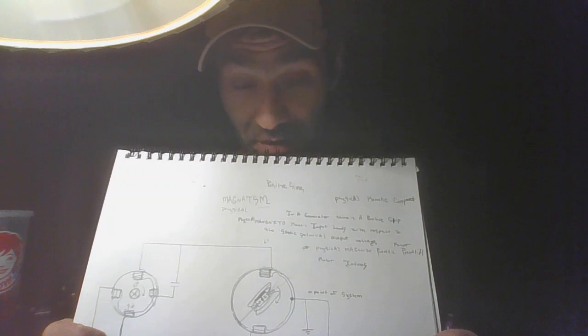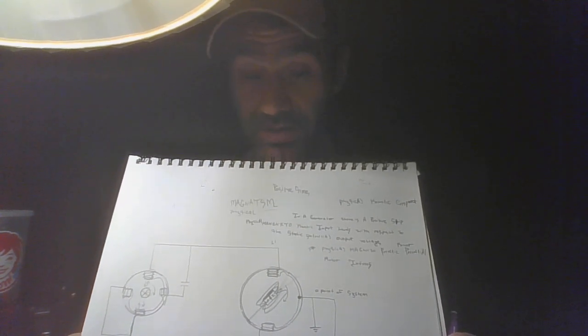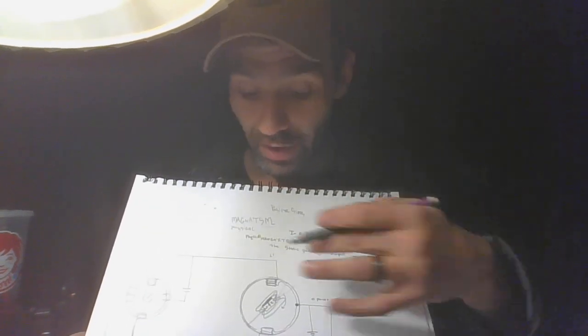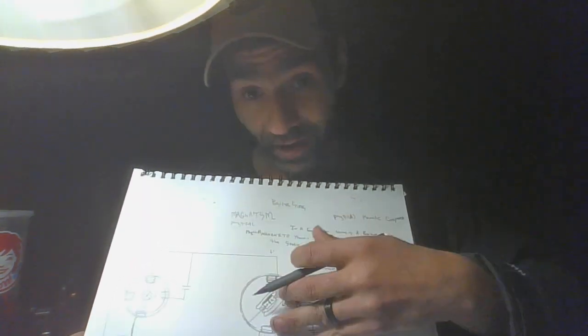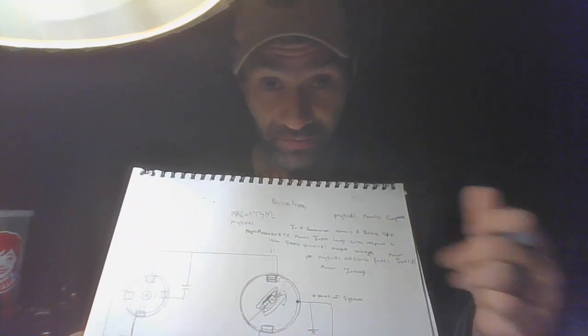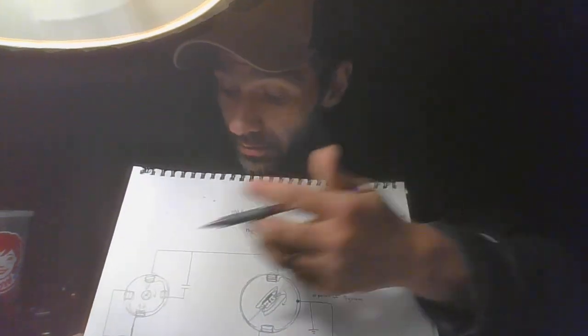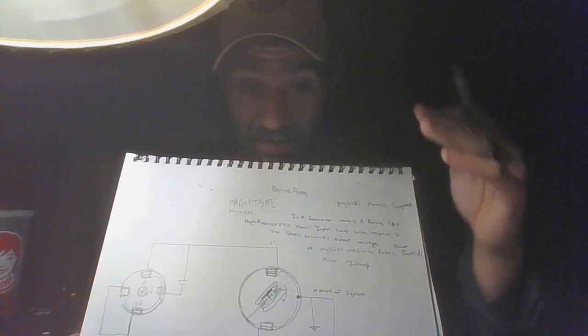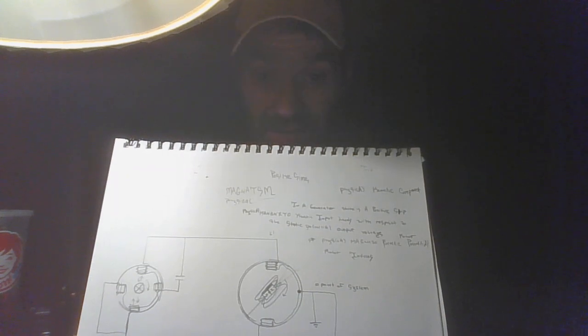We can't get 360 degrees of rotational torque out of it. We cannot create 360 degrees of rotational torque with a single phase supply, because we only have 180 degree in-phase displacement. We don't have a phase to phase voltage. We have to have phase to phase voltage between these windings to create the phase angle kick that's required for 360 degrees of rotation. Now, there must be this lag in an electric motor. The rotor, the donkey, must stay a certain distance behind the carrot. And if the donkey ever catches up to the carrot, there's zero torque on the rotor. And if the rotor outruns the stator's RPM, then the stator will start collecting energy, or back EMF, and it will become a generator.